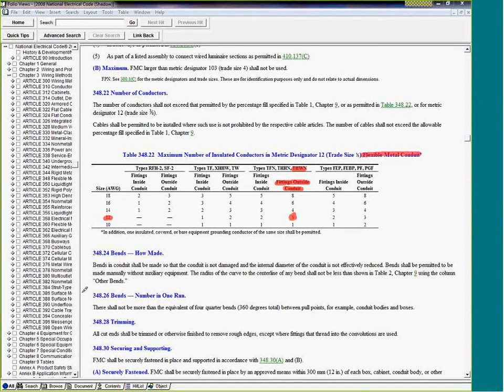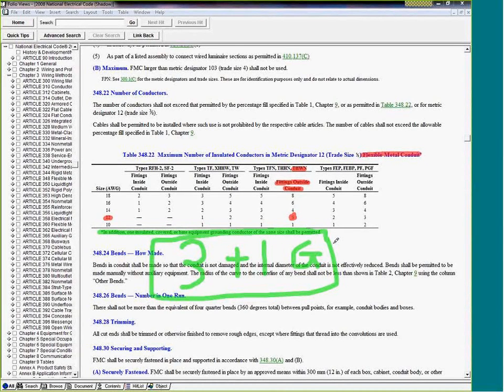I want to bring to your attention that they always get you on the test right in here. In addition, one insulated, covered, or bare equivalent grounding conductor of the same size shall be permitted. So, my friend, how many conductors can I really do? You're going to tell me 3 conductors plus 1 conductor ground. That's the answer. So it's 4 conductors including the ground: 3 conductors and 1 conductor covered, insulated, or used for ground. So all of them THWN number 12 in a 3/8 inch will be 4. If they ask you how many conductors you can fit, no ground, the answer will be 3. Very interesting. Make sure you know how to use this table, because it's a new journeyman exam.